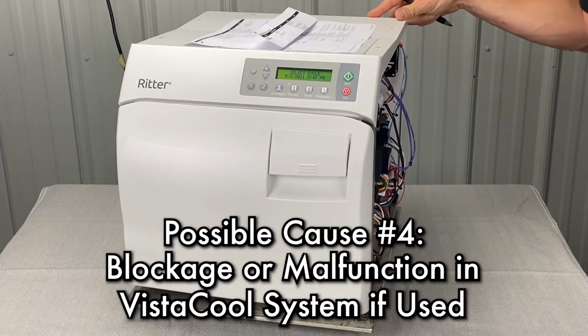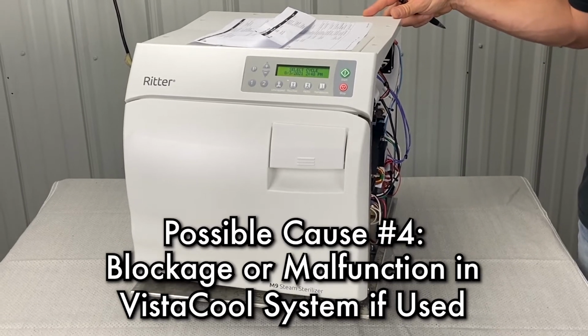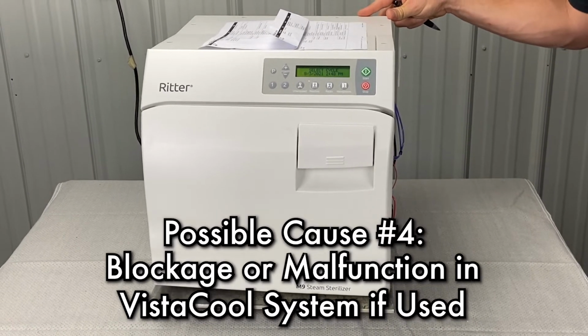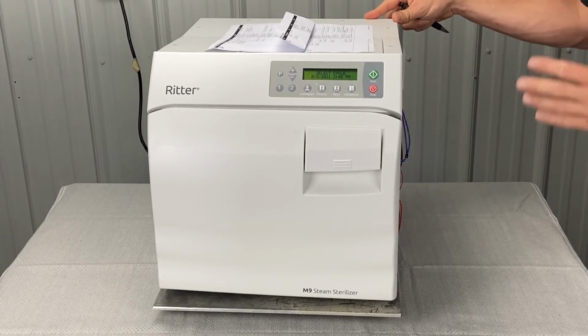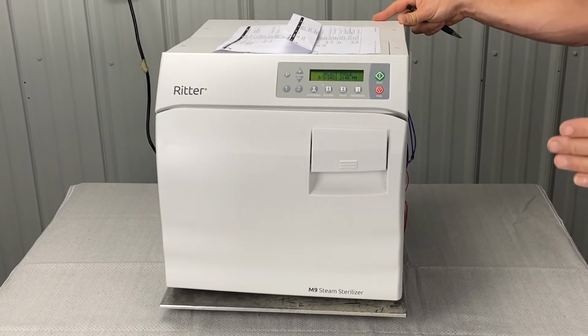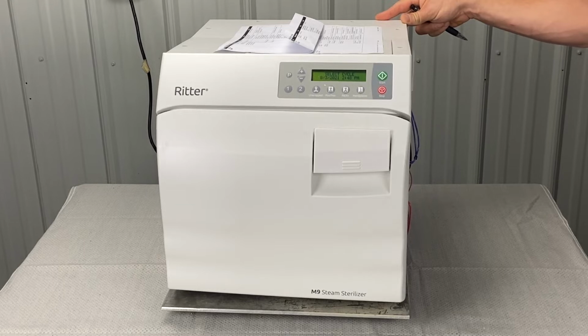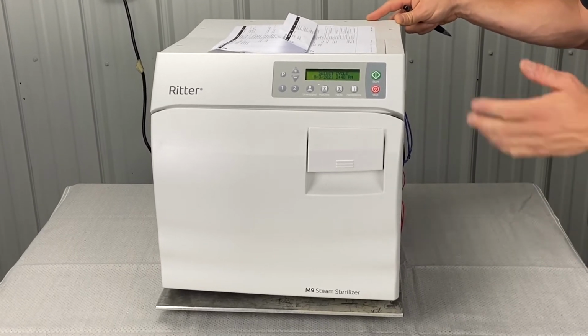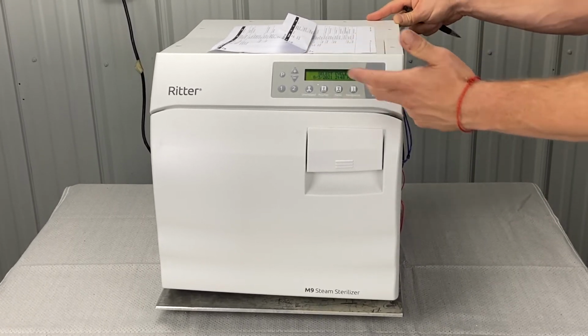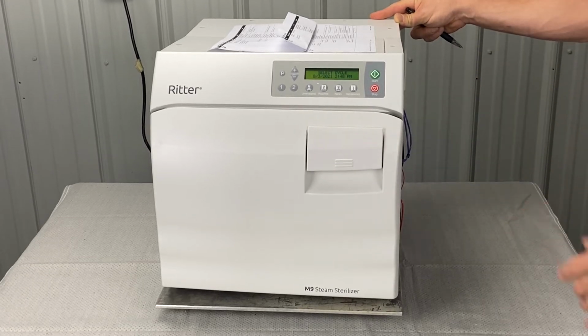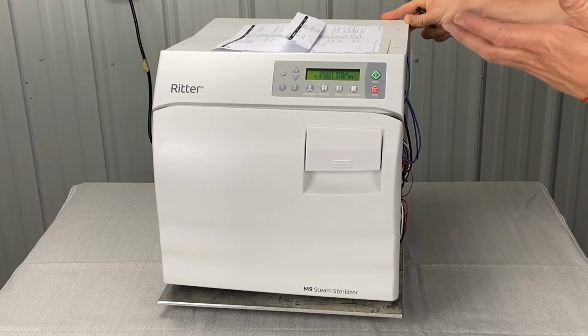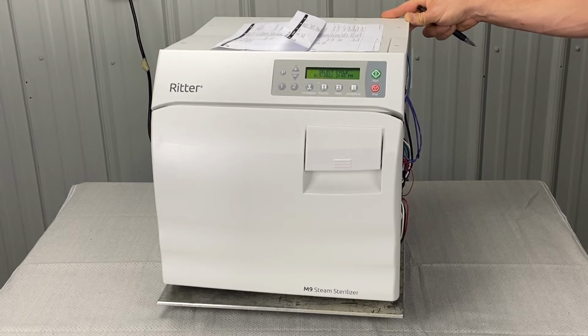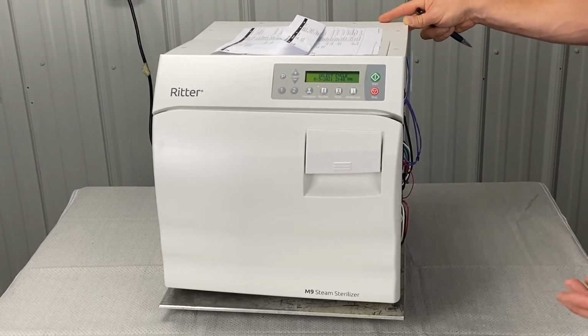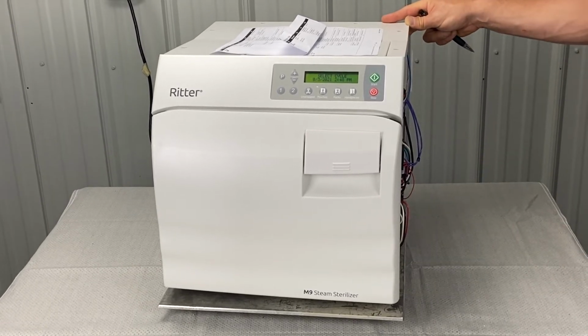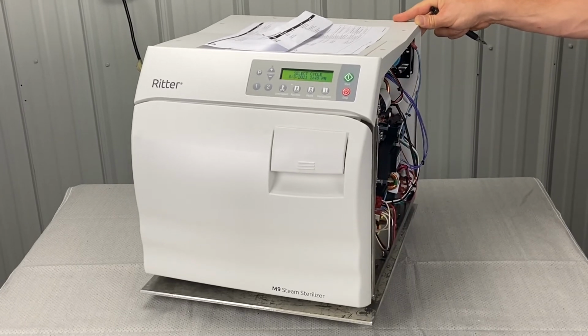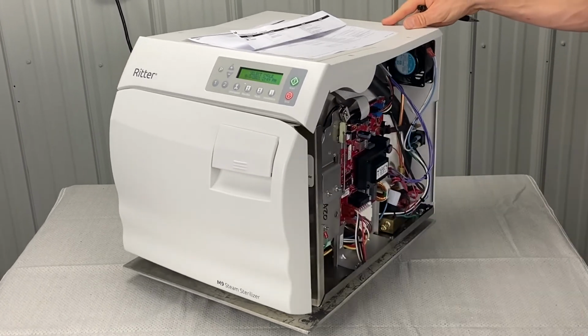Okay, blockage or malfunction in VistaCool system. If you have a VistaCool, then we'll have to go down this road. If you do not have a VistaCool, what I would do is pull all the instruments out, run an empty cycle and start it, and then just watch the screen, see where your temperature and pressure go. If it starts to build up to about 250 degrees and about 15-20 psi, and then all of a sudden the psi starts dropping without the solenoid engaging, then it's probably defective.